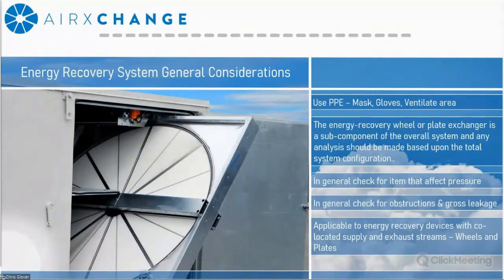In general, you're going to look for items that affect pressure, any potential airflow obstructions, or areas of gross leakage or recirculated air. The suggestions that I'm going to demonstrate here are based on the energy recovery technologies that have airstreams that are co-located next to each other. So it's traditionally wheels and plates.